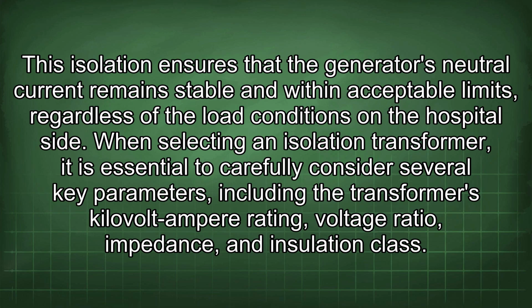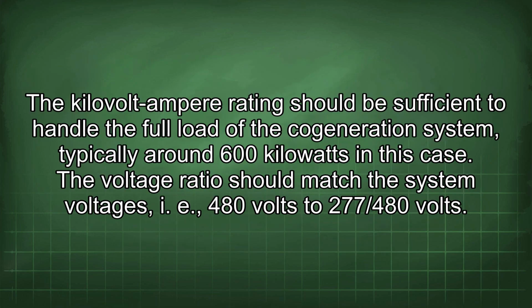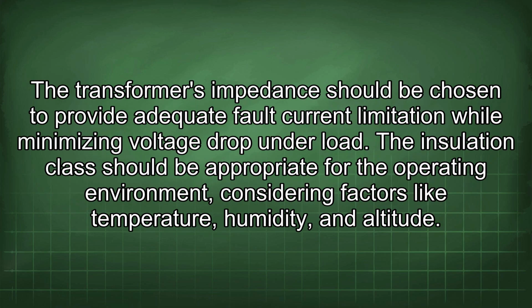This isolation ensures that the generator's neutral current remains stable and within acceptable limits regardless of the load conditions on the hospital side. When selecting an isolation transformer, it is essential to carefully consider several key parameters, including the transformer's kilovolt-ampere rating, voltage ratio, impedance, and insulation class. The kilovolt-ampere rating should be sufficient to handle the full load of the cogeneration system, typically around 600 kilowatts in this case. The voltage ratio should match the system voltages, i.e. 480 volts to 277/480 volts. The transformer's impedance should be chosen to provide adequate fault current limitation while minimizing voltage drop under load. The insulation class should be appropriate for the operating environment, considering factors like temperature, humidity, and altitude.